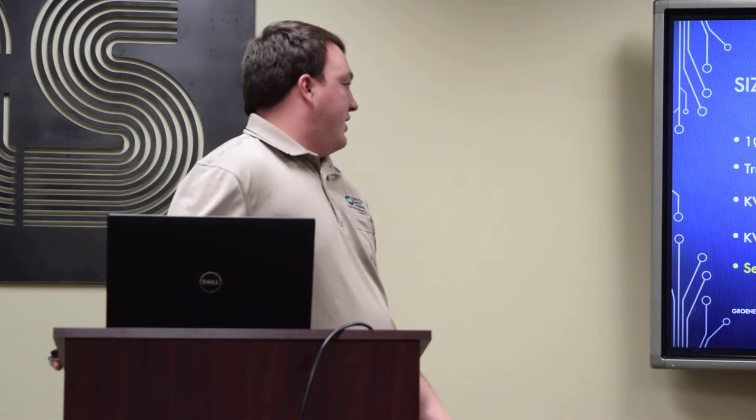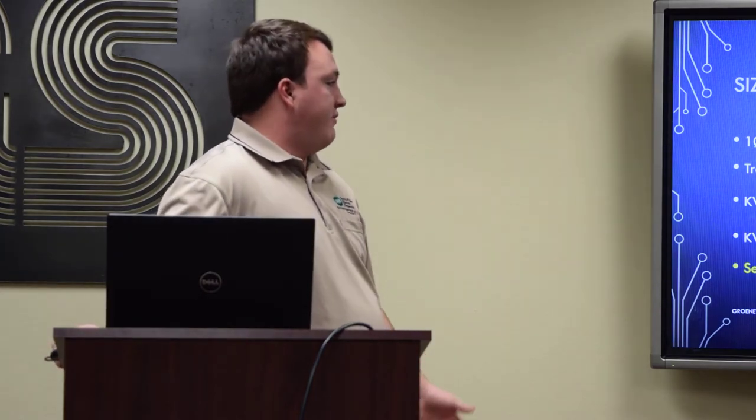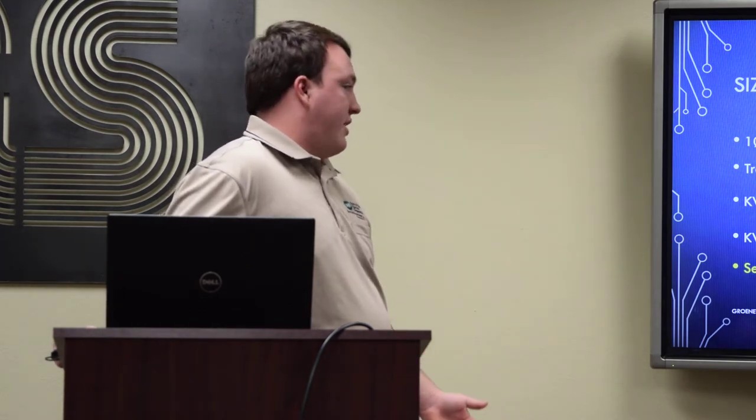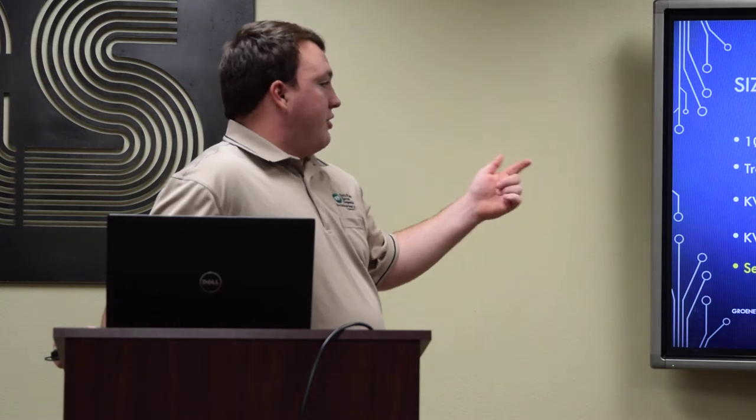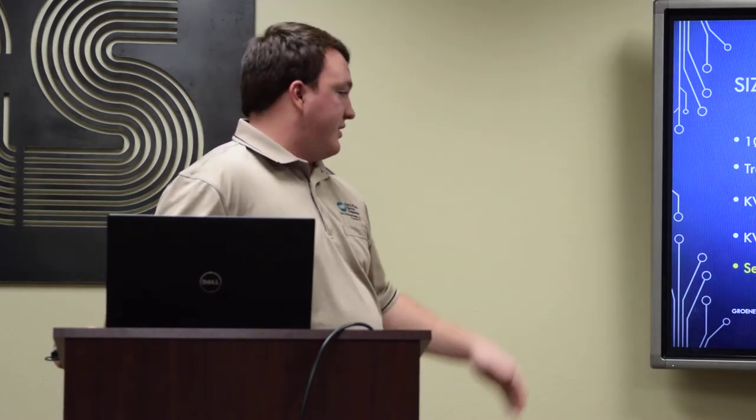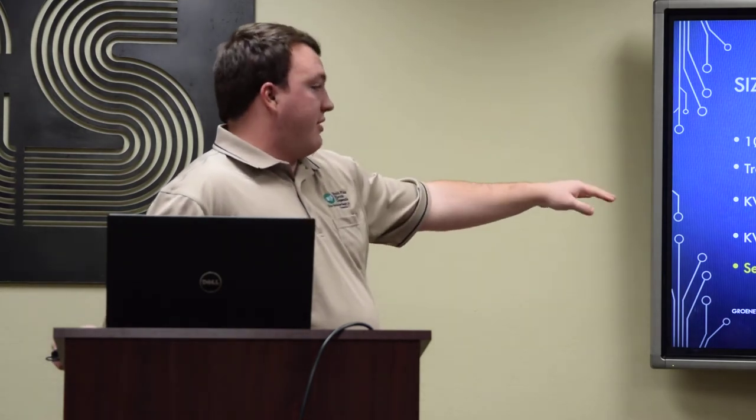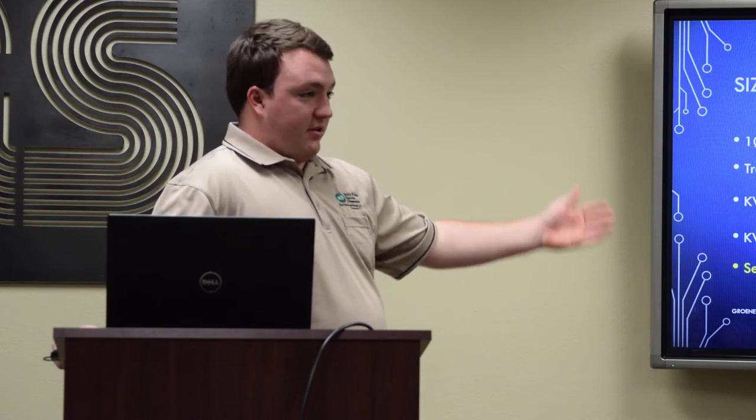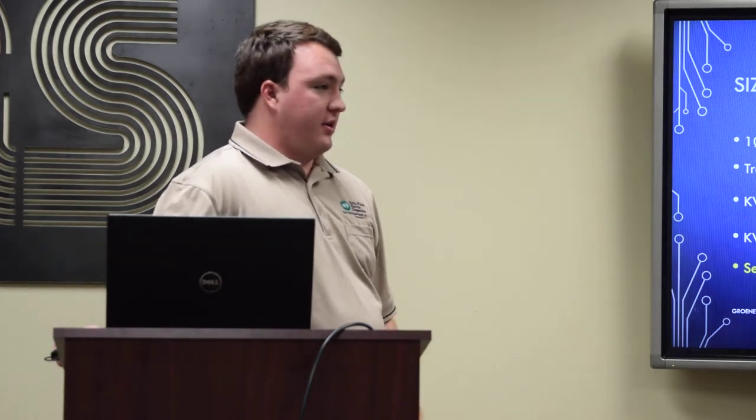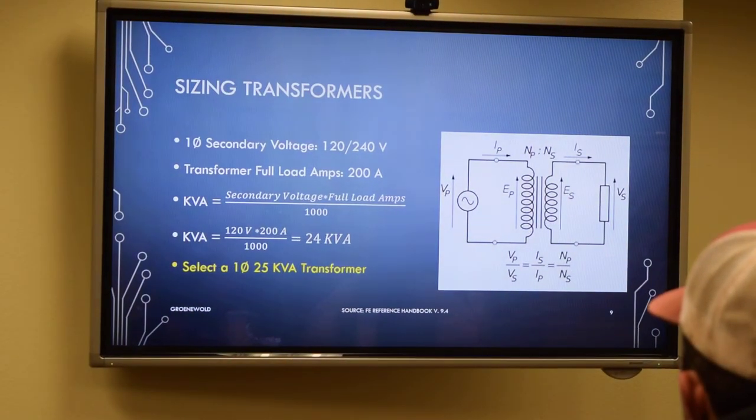An example on sizing your transformers, if you have a single phase secondary voltage of 120/240, and a member says, hey, I want a 200 amp service, you would just multiply the 120 times your 200 amp service and divide by 1,000 to get your kVA rating for your transformer, which would come out to 24 kVA. We don't have any of those, but we do have a 25 kVA transformer. That's why a 200 amp service is why we hang a 25 kVA pot.